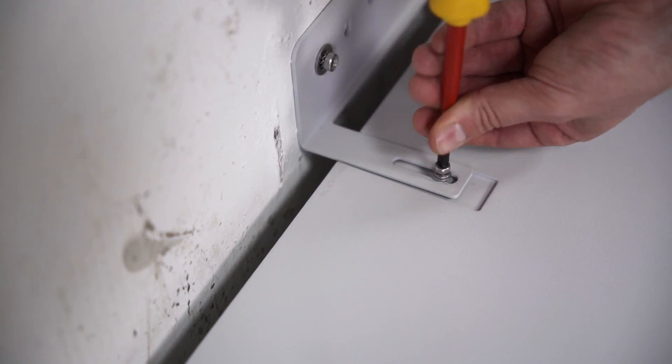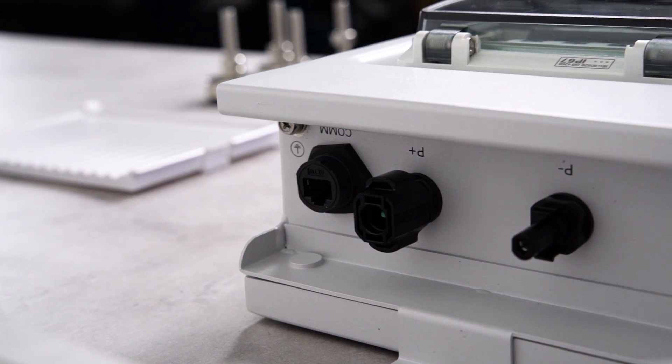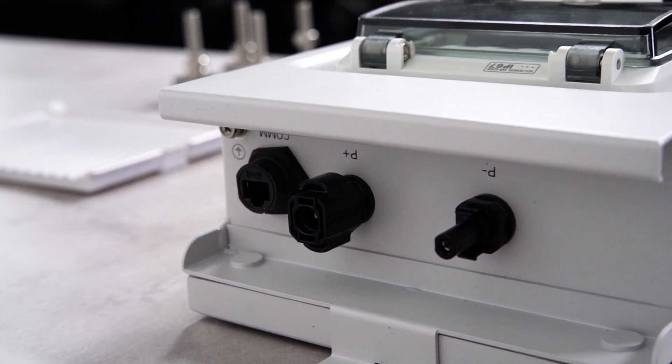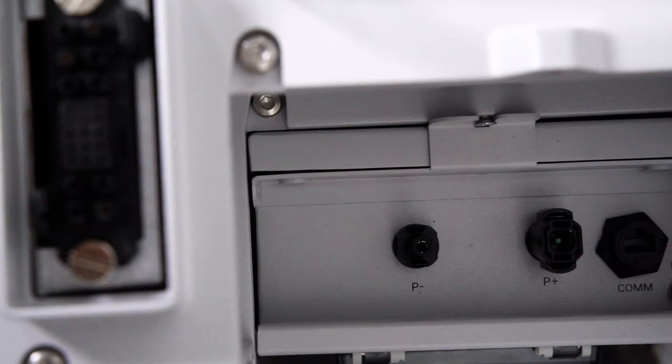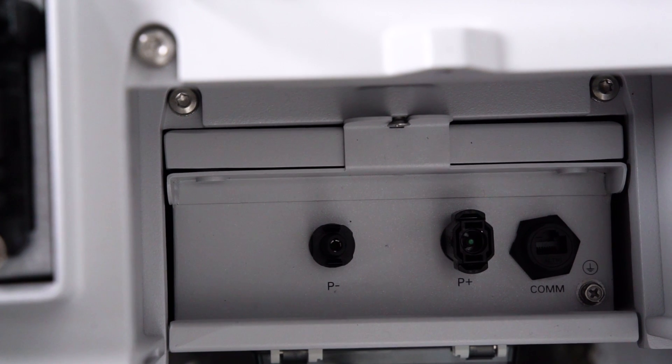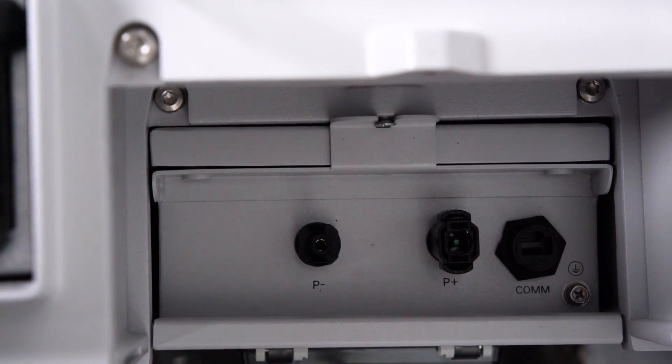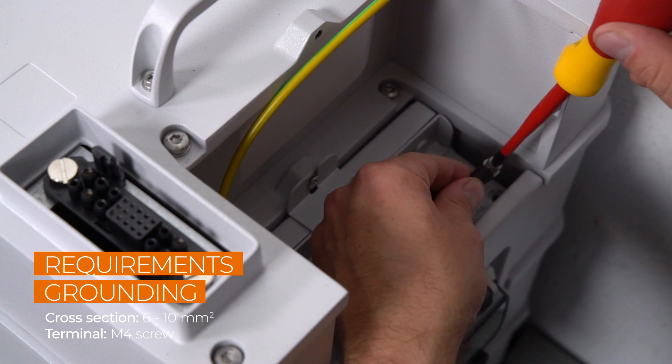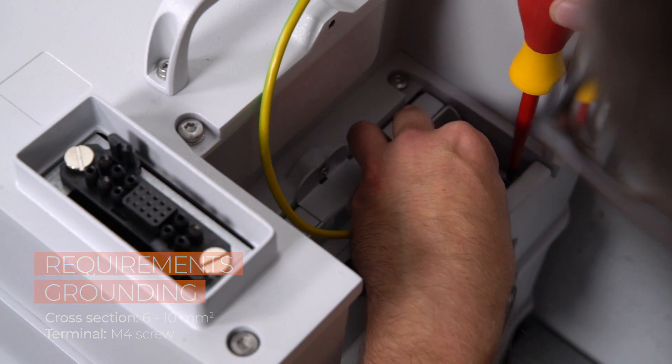Now let's come to cabling. The battery has four connectors: grounding, P plus, P minus, and one terminal for communication with the hybrid inverter. Let's start with the grounding. Fix it on the battery side and connect it to the ground at the bottom of the inverter.